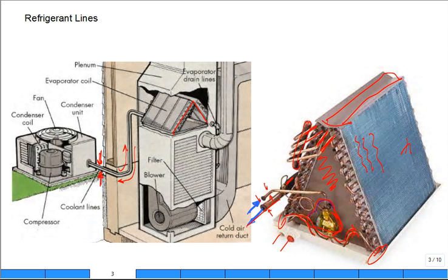The length of this line between the expansion valve and the evaporator coil is very short. Likewise, back here is the compressor. The suction line goes to the compressor. Then it discharges from the compressor and starts to go into these condenser coils. It then comes out of the condenser coil, goes through a filter dryer, and the liquid line back up into the house. So, the length of the line connecting the compressor and the outdoor condenser, condensing coil, is very short. There's two long lines. See that? And two very short lines.